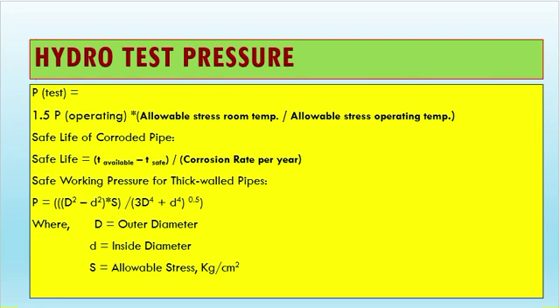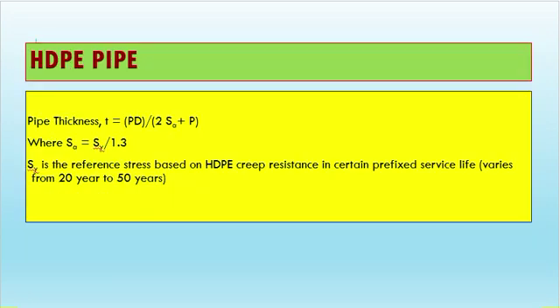For safe working pressure of a thick-walled pipe, the formula is: P = (D² − d²) × S / (3D⁴ + d⁴)^0.5 × 0.1, where D is the outside diameter, d is the inside diameter, and S is the allowable stress in kg/cm². So three formulas are now covered: hydrotest pressure, safe life of corroded pipe, and safe working pressure for equal-wall pipe.